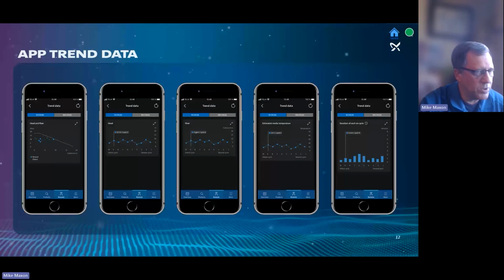You can see where the pump's been running, where the last 10 cycles are. It doesn't have a clock in this one, so it doesn't know how long it's been off. It knows how long it's been on, but it doesn't know how long it's been off. So we could look at the last 10 cycles, what the head, what the flow, and what the temperature, and what the cycle times were. Or we could look at the last 100 cycles. The last 100 cycles is a conglomeration of 10 cycles, 10 cycles, 10 cycles over and over again.